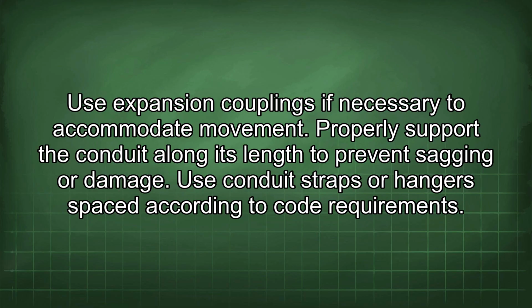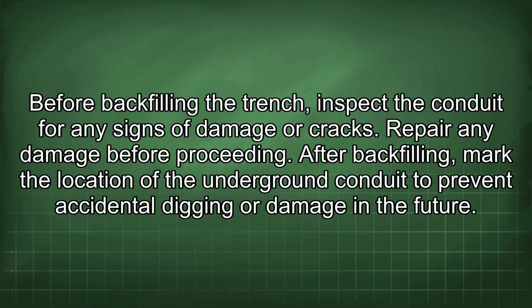Properly support the conduit along its length to prevent sagging or damage. Use conduit straps or hangers spaced according to code requirements. Before backfilling the trench, inspect the conduit for any signs of damage or cracks. Repair any damage before proceeding. After backfilling, mark the location of the underground conduit to prevent accidental digging or damage in the future.